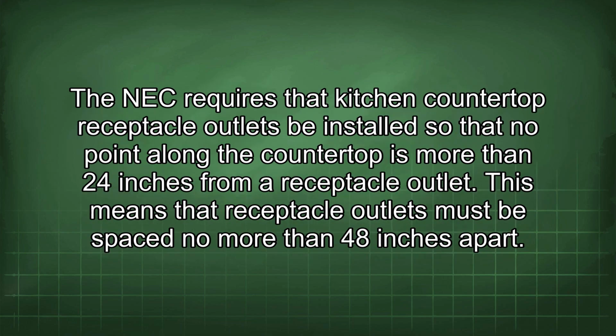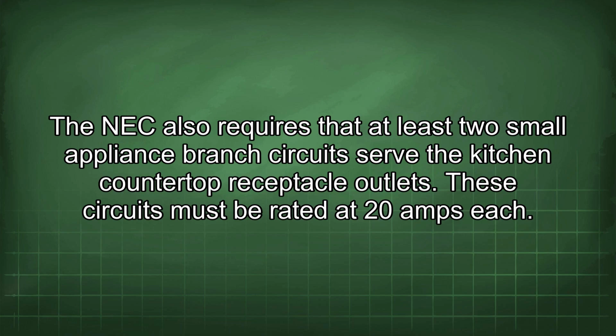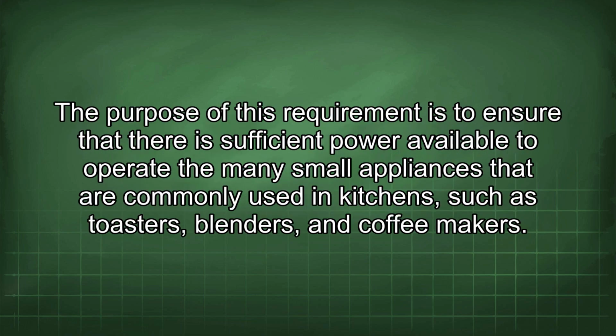The NEC requires that kitchen countertop receptacle outlets be installed so that no point along the countertop is more than 24 inches from a receptacle outlet. This means the receptacle outlets must be spaced no more than 48 inches apart. The NEC also requires that at least 2 small appliance branch circuits serve the kitchen countertop receptacle outlets. These circuits must be rated at 20 amps each. The purpose of this requirement is to ensure that there is sufficient power available to operate the many small appliances that are commonly used in kitchens, such as toasters, blenders, and coffee makers.